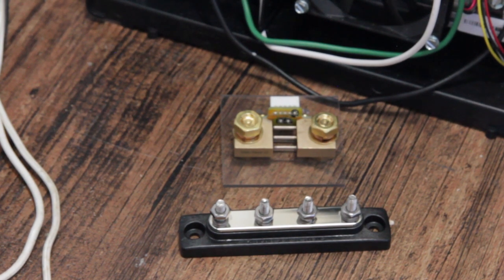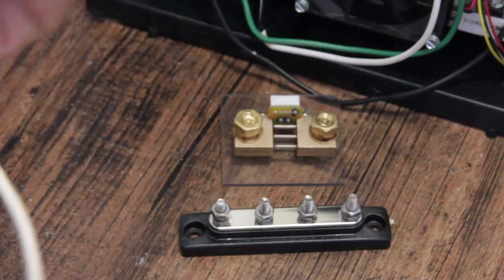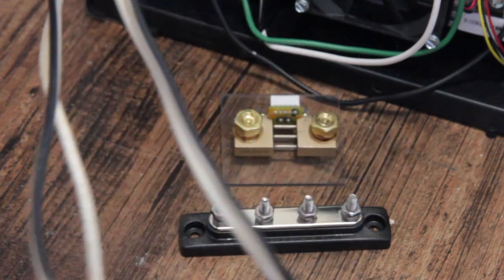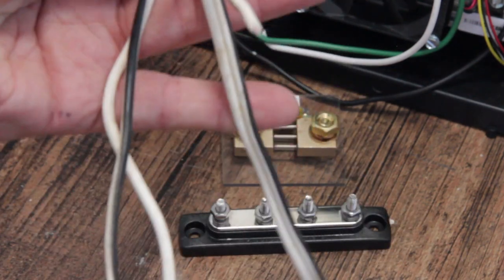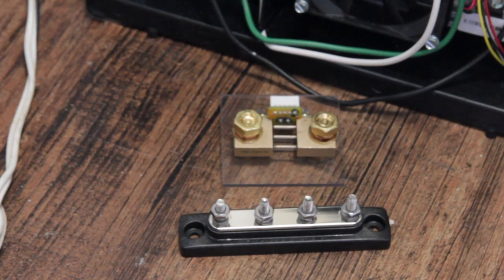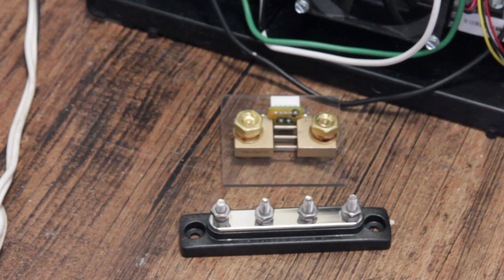I'm going to run a ground wire from the ground bus through the shunt out to all the DC loads. I don't want to track the capacity of the AC circuits, but I do want to capture my current usage across all of my DC circuits. I'll show you how we're going to wire that shunt and bus bar into the power converter so we can monitor the capacity and status of our battery when we are using battery power.